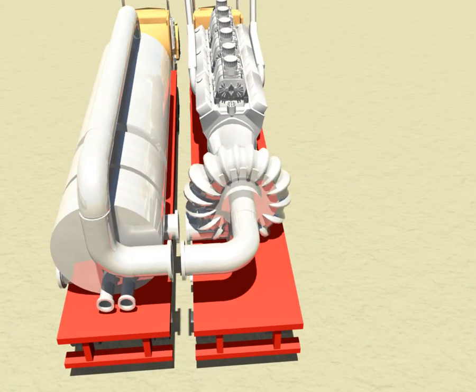A 1 megawatt natural gas-powered compressor recompresses about 75% of the vapor stream to liquid. The remaining vapor stream is recovered as MVR vapor distillate. The recompressed vapor stream is returned to the heat exchanger by the evaporative tank to provide heat to the liquor. This stream exits as a high-temperature liquid stream. The pressure is dropped to return this liquid stream to vapor, where it is mixed with the original vapor distillate stream. This mixed vapor stream is sent to provide heat to the feed preheater.